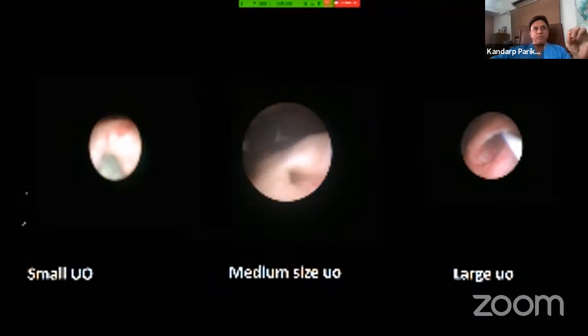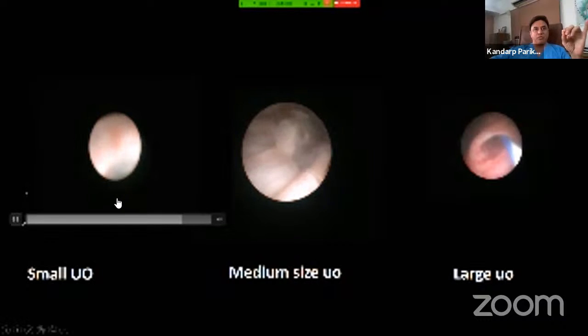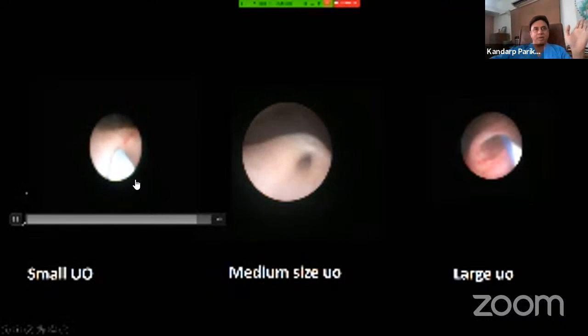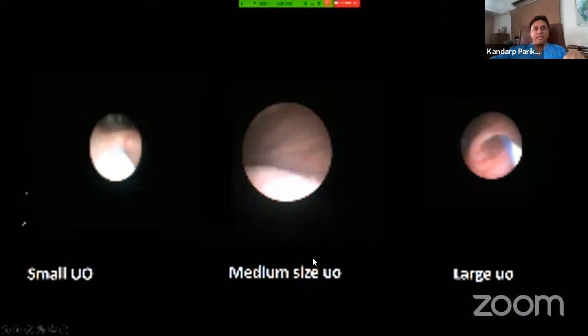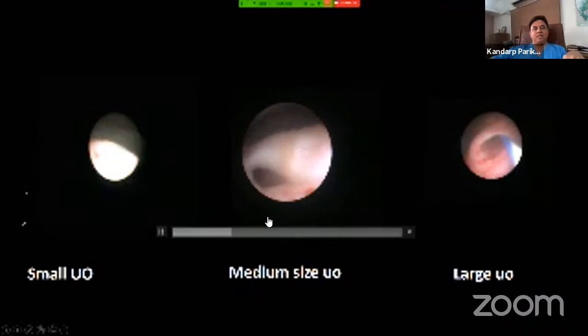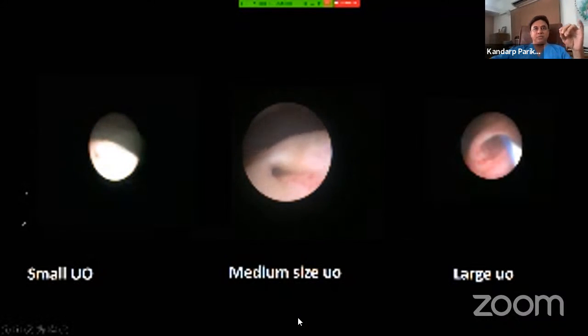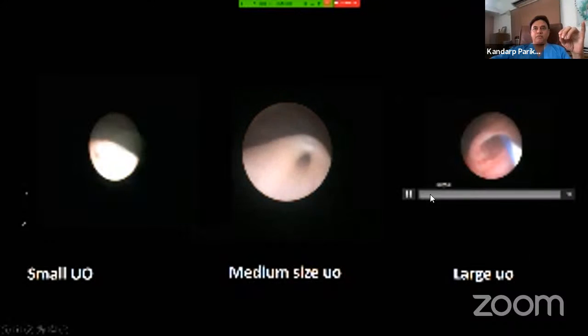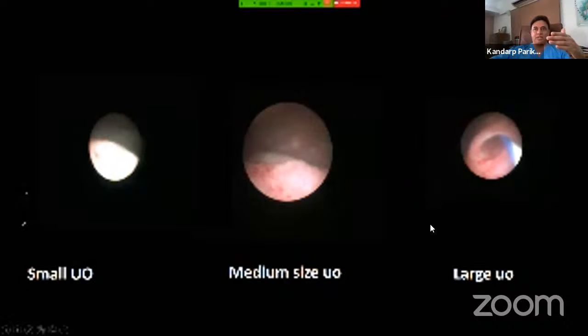So you may be required to use a balloon dilator or a Teflon dilator to dilate the UVJ, or you may put the double J stent and come out and go next time. When it is a medium-sized ureteric orifice like this, it is possible that you will be in a position to put a 9.5 French or 10 French ureteral access sheath. And if you have a larger ureteric orifice like this, in that case, it is possible to put an even larger sheath. You usually get this after dilating with the balloon, or if the patient was pre-stented.